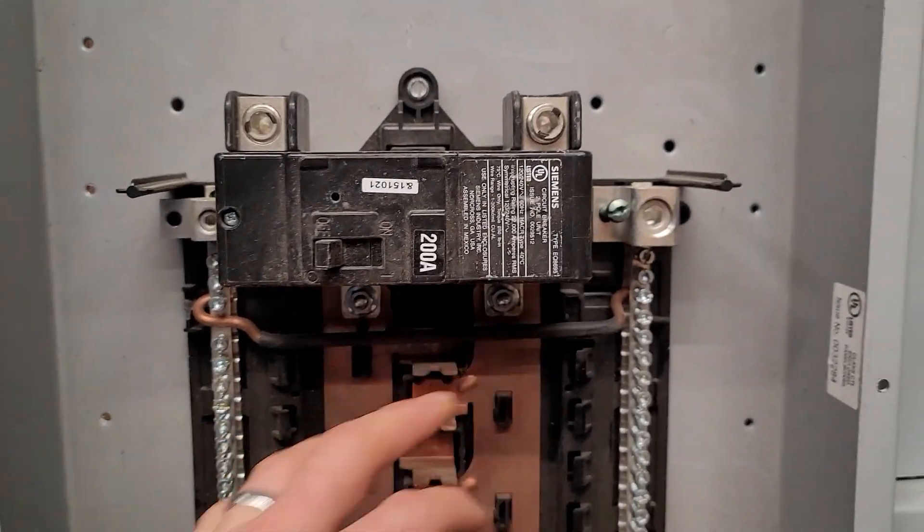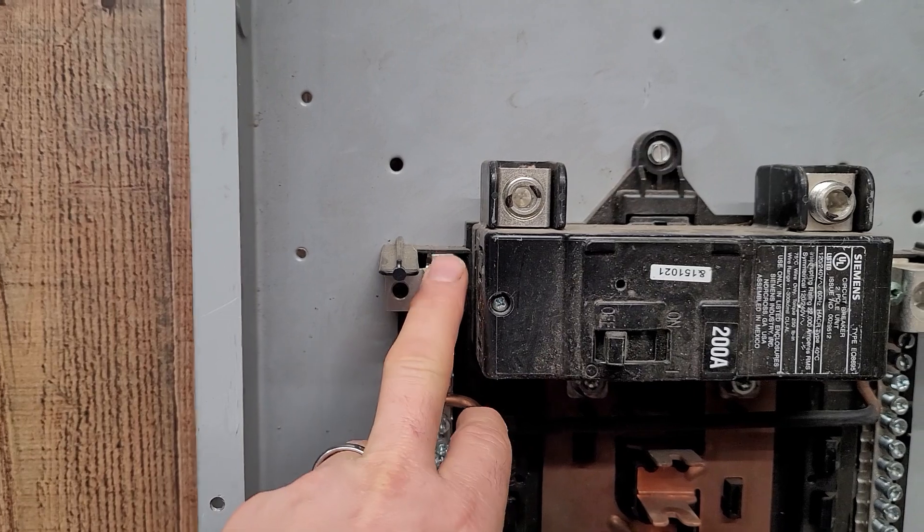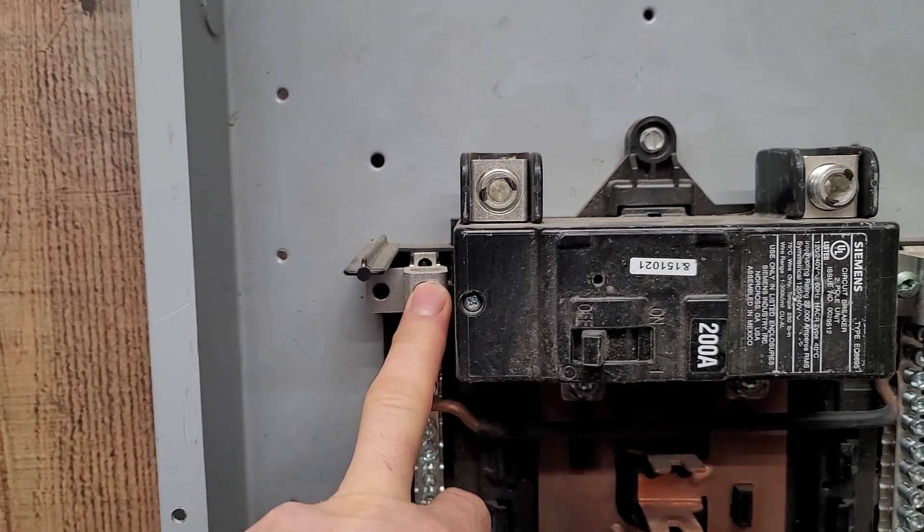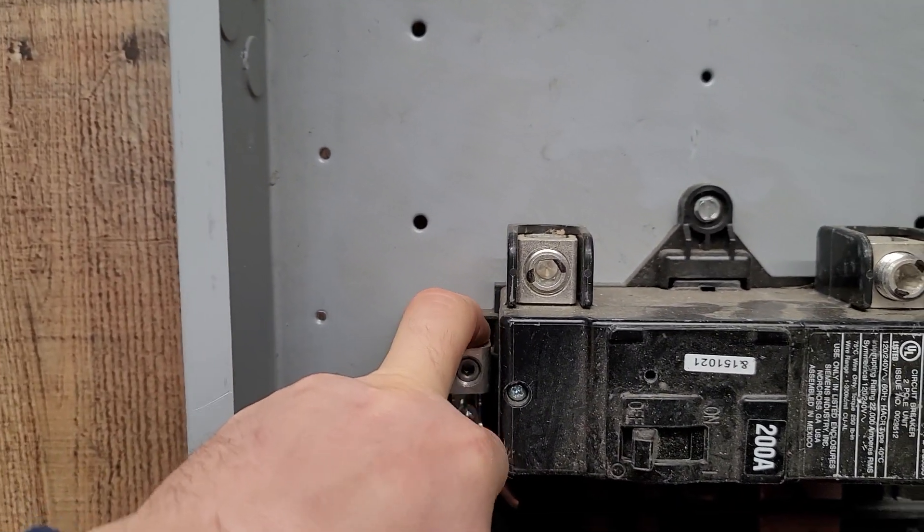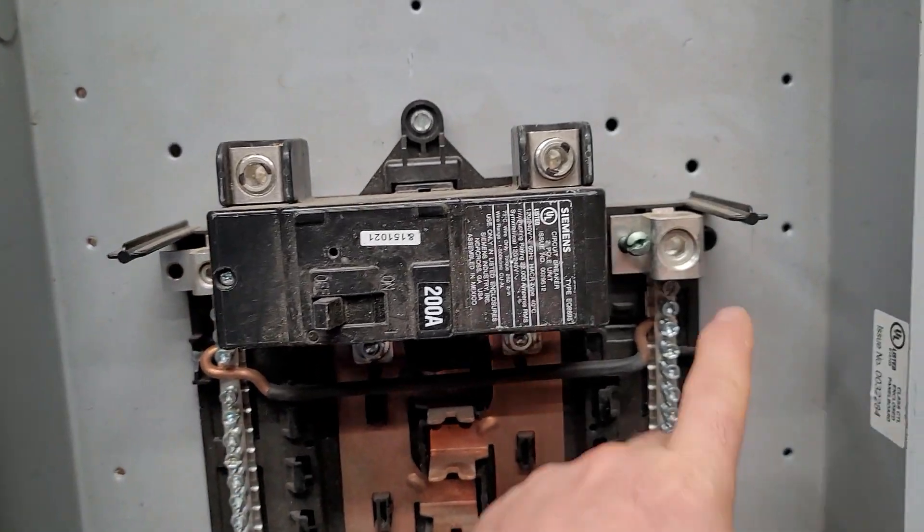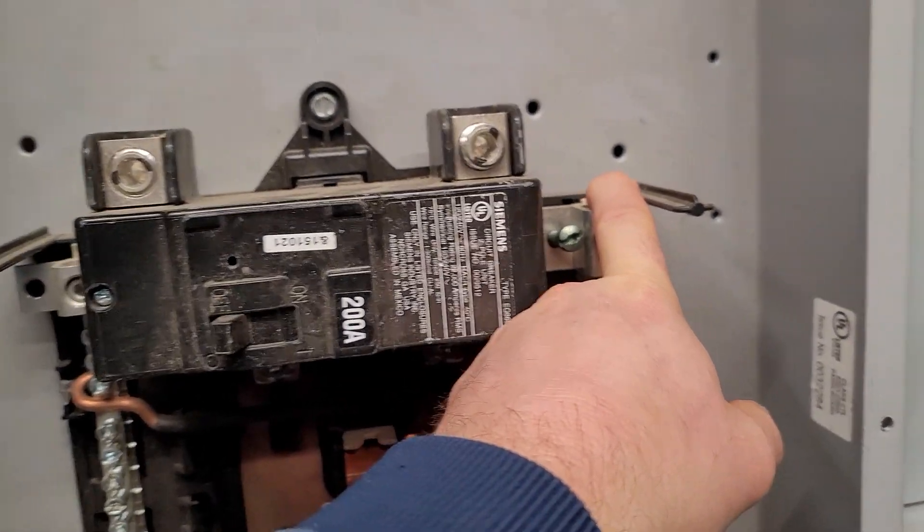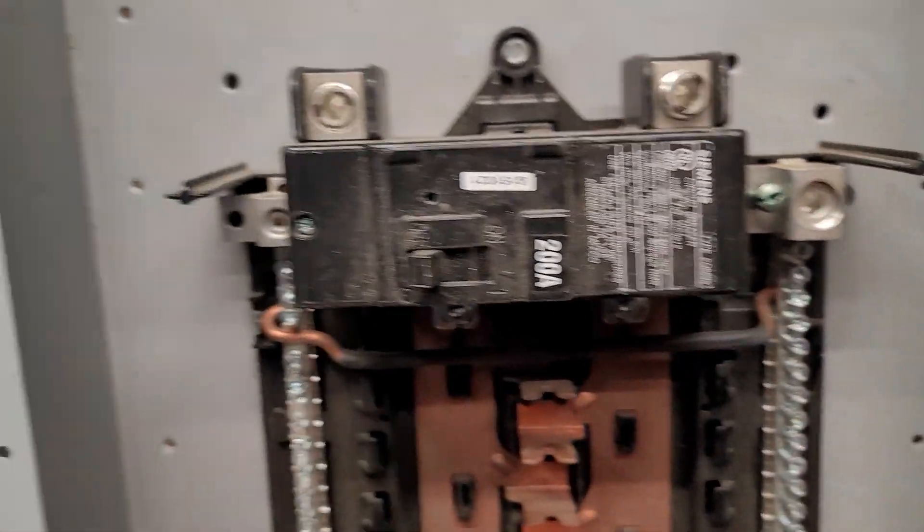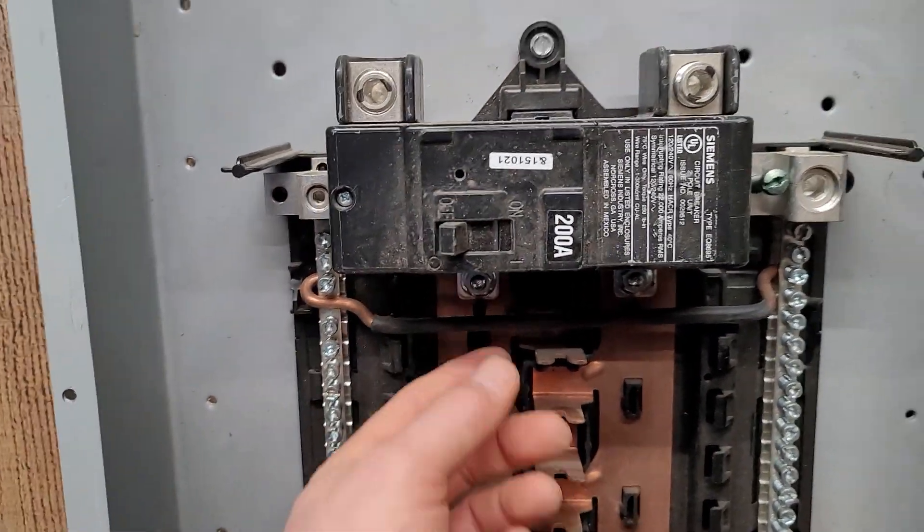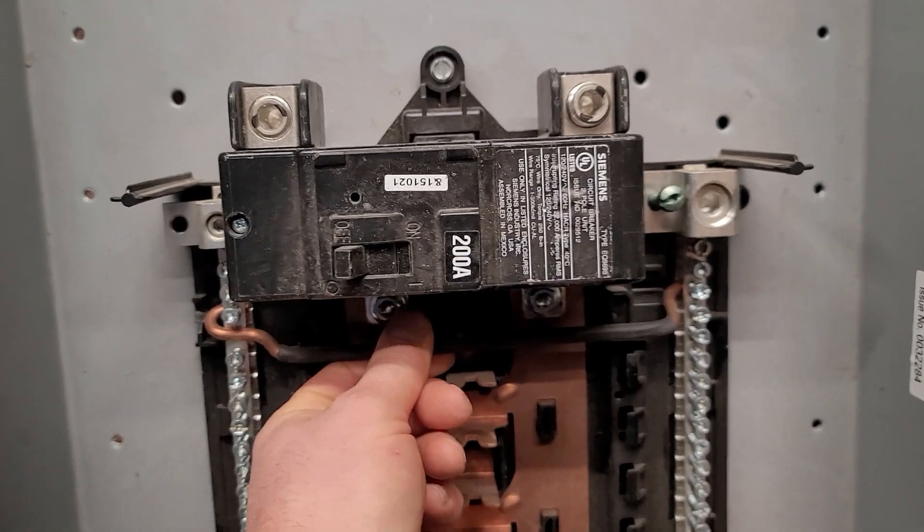Well here's the problem with that. You end up with a smaller terminal right here to land your neutral. It's not going to be big enough to land your neutral. You would have this larger one over here which would seat your ground fine, but you're going to end up with a smaller neutral terminal and likely this can is not listed to remove this right here.